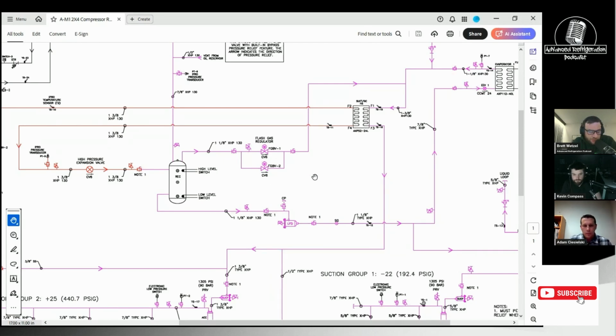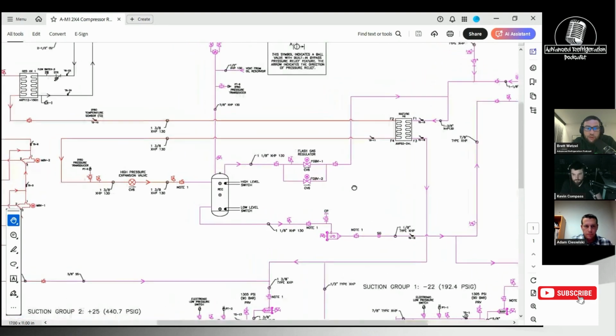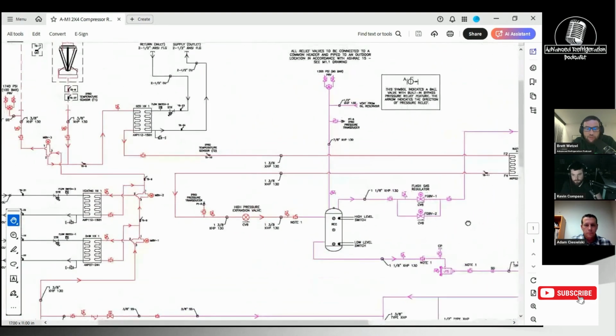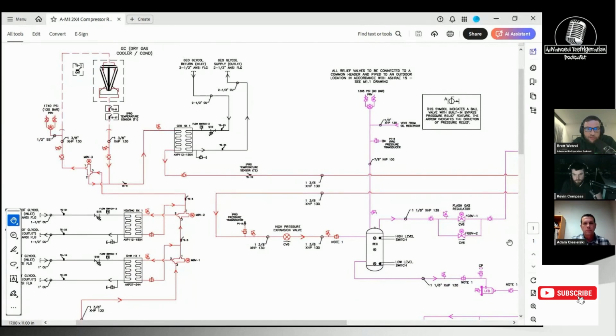Okay. Because I know on the bigger industrial systems, they're starting to have a little bit more redundancy as far as valves. Yes, you might need to put another one in there as far as size. But what I've seen is they'll do redundant valves, HPV and BGV, because those are the heart of the system. Without both of those, you're going to be dead in the water if one of those were to fail. Yeah. Gotcha.